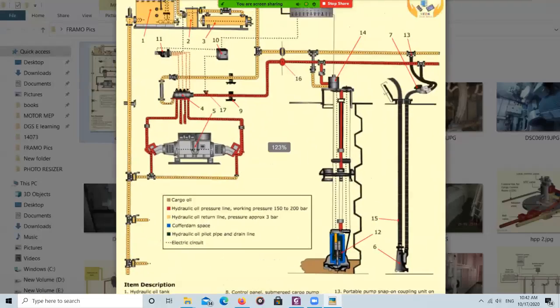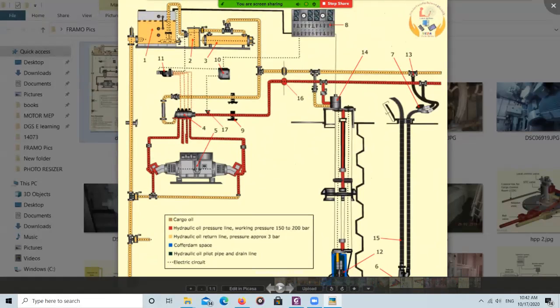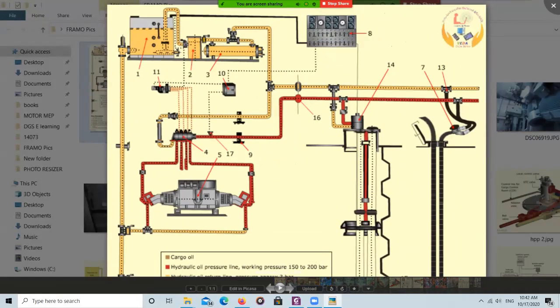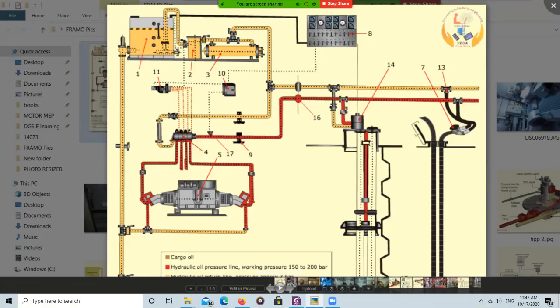This is the in-depth system view. From the hydraulic oil tank there will be a number of feed pumps — also called jockey pumps — fitted on top of the hydraulic tank. Their main function is to keep the whole hydraulic system in positive pressure, so 24/7, 365 days, one pump out of three will always be running. This is to ensure the system stays in positive pressure, and also to prevent air from entering, because if air goes inside there will be problems with the suction of the main variable displacement pump.